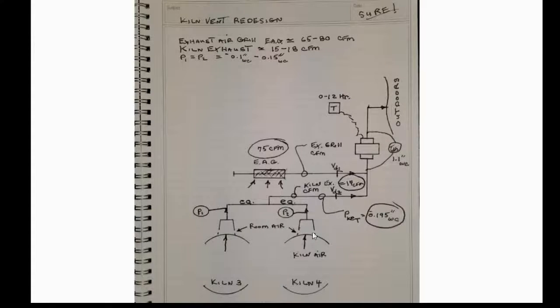Key for us was to get 17 CFM. So we just dropped this volume damper until we got P1 and P2 where we want it, which was about 0.15 inches negative, which resulted in about 0.195 inches at this point. So I gave my test port and marked it. Then this volume damper is completely open. This volume damper is ever slightly closed to get our required pressures. And then both of them are screwed down and then taped over. So there's very little that could go wrong with this. And we would expect this fan to last them on the order of 5 to 10 years, maybe longer. But it's super quiet, super efficient.